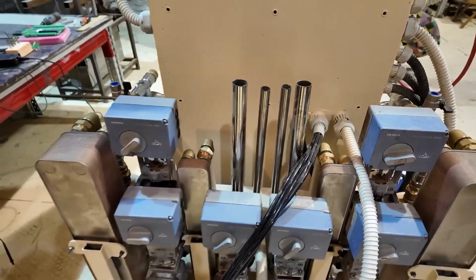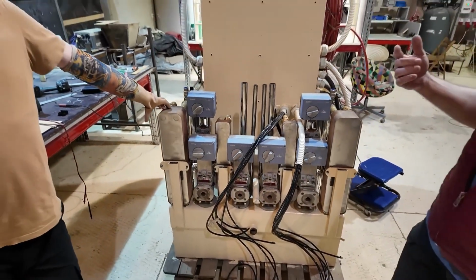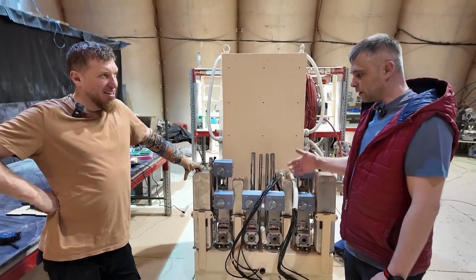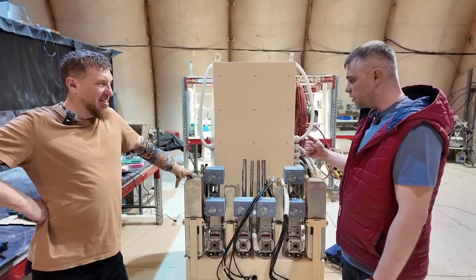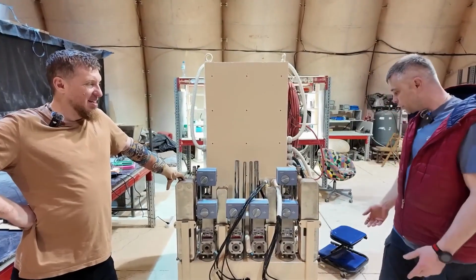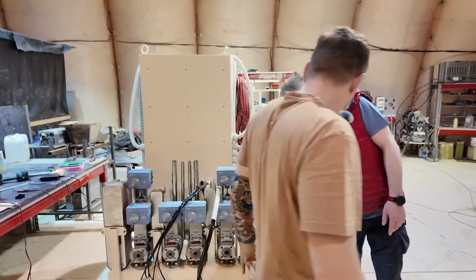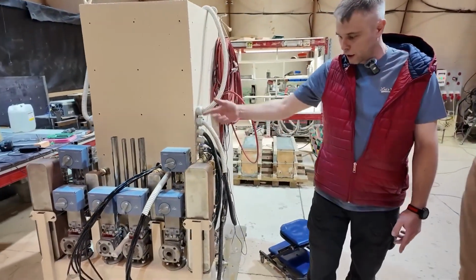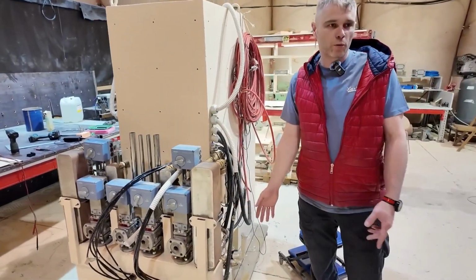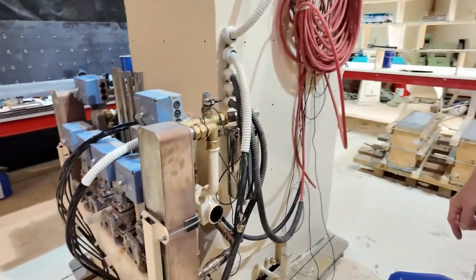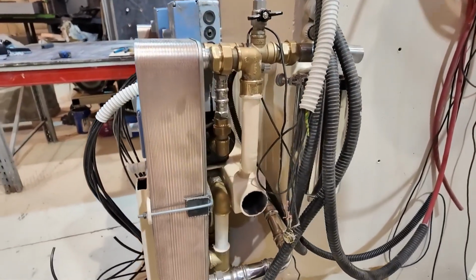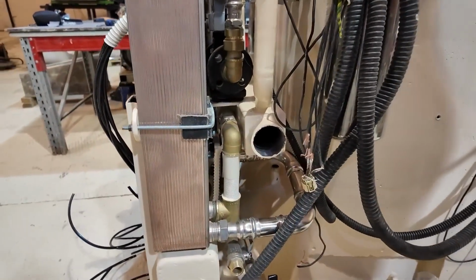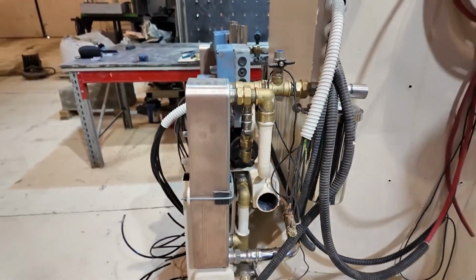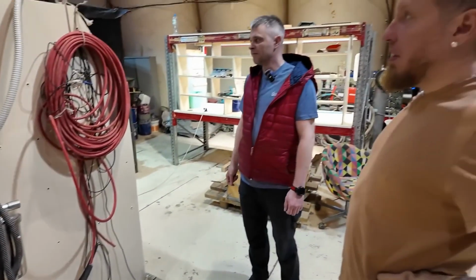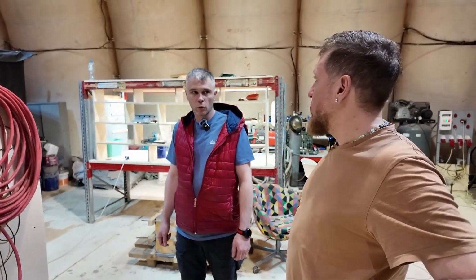And how are we going to handle the recuperation of the generated energy? Yes, we will return the energy back to the test stand itself. If we have too much excess energy, if the voltage is too high, we have a water drain, and there will be 2 powerful heating elements installed on this and that side where we will dump all the surplus energy. Because if the lower motor starts generating, there will be too much voltage. For example, it's 400, but we're testing a 90-volt motor. Well, so everything will be fine.